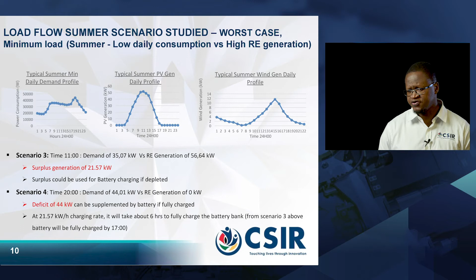So what do we take away from the load flow studies assessment that we did? It is that the load flow study by itself has limitations, because of this mismatch in load and generation. This particular condition calls for generator optimization studies that are time-based and can be done over the entire year to actually see the generation production together with the demand, whether the generation supply is enough to meet the demand in the area.